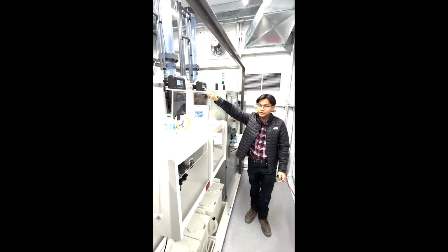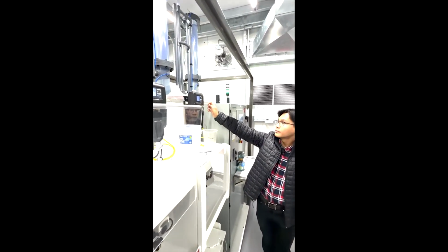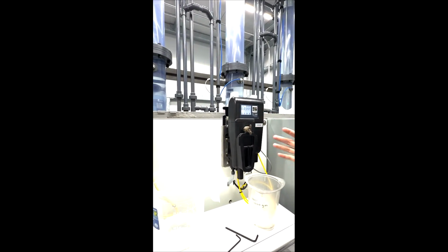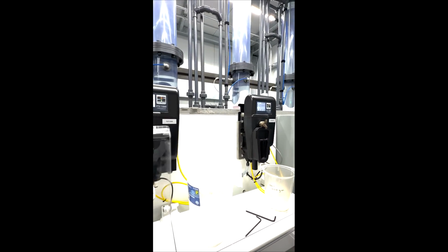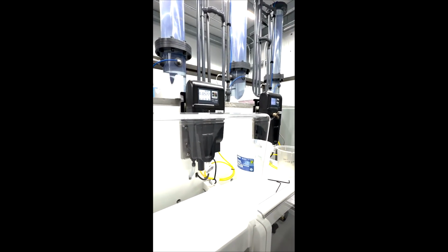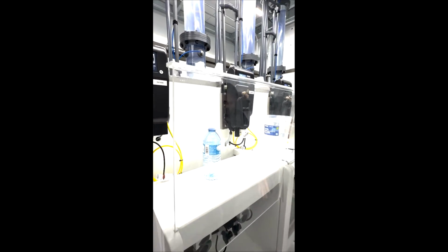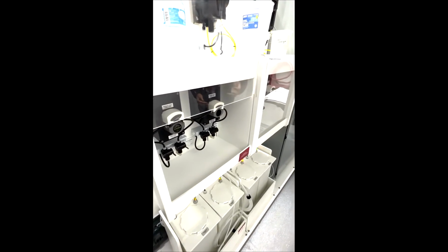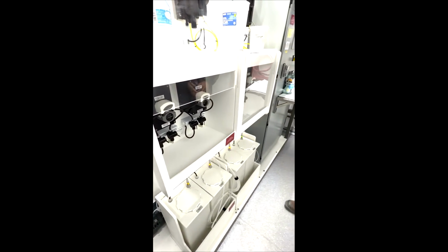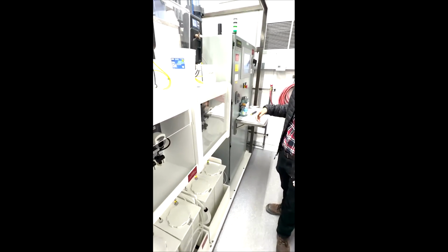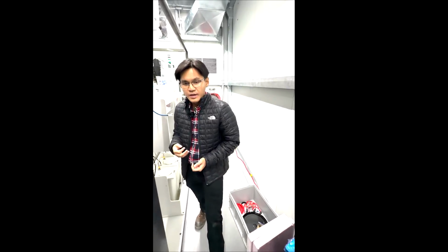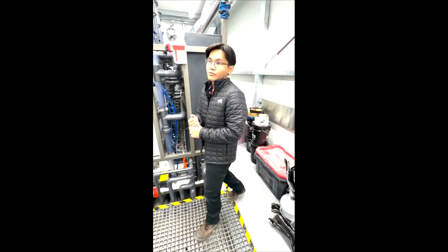And then we can also measure how cloudy the water is. As you can see here, we're seeing some very good performance. You could see in the other building it was like 0.2. Now we're getting to 0.03. And we also have the option to dose chemicals if we want to increase the performance or disinfect the water through these pumps over here. And so eventually all of this water that's put through not just the DAF system but also the filter system is brought outside, and I'll show you how that system works now.